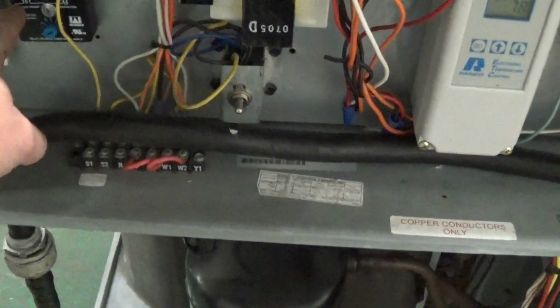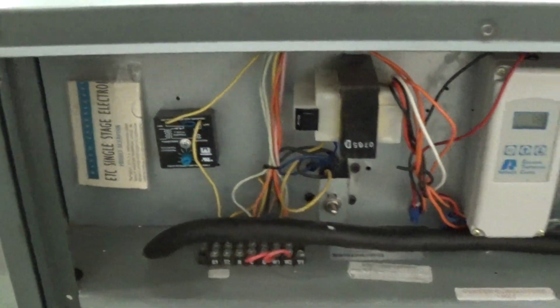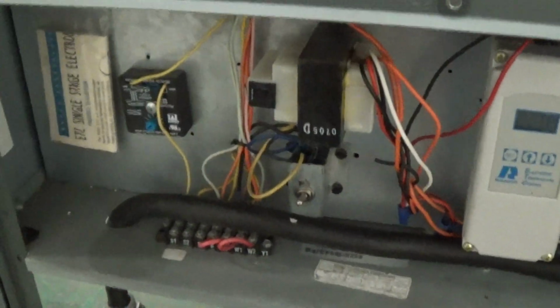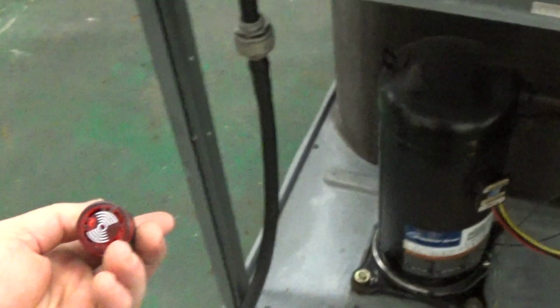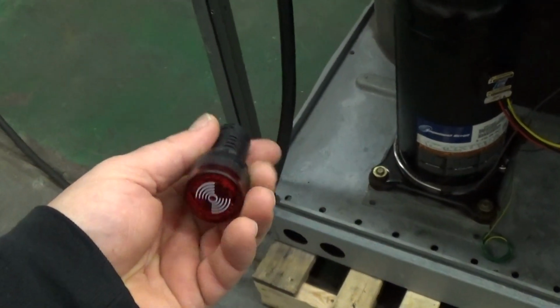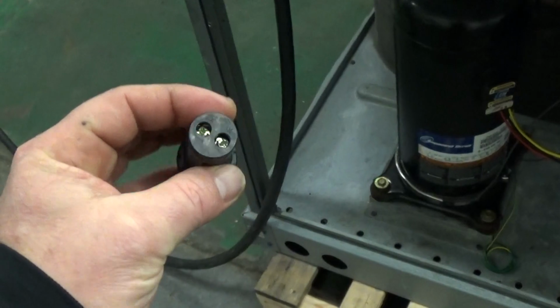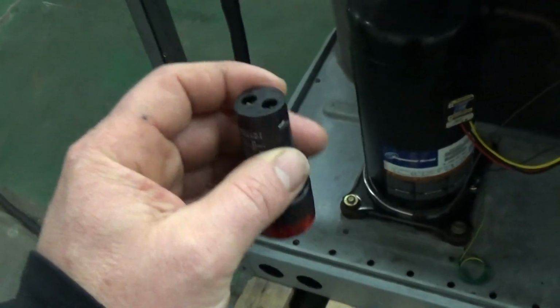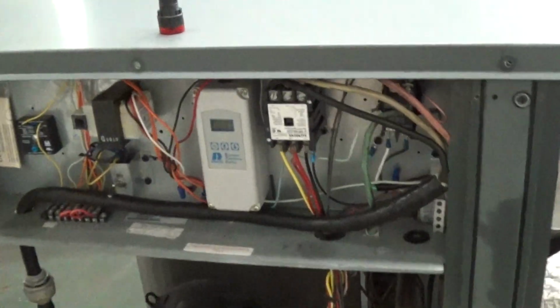And here this is actually a timer that's going to be dedicated to the glycol level switch. We're going to either mount or ship loose with some wiring this alarm and buzzer, and that's tied into this delay timer right here, okay? And so if by chance your glycol gets too low, there's a little float switch in here. It'll set off that alarm and buzzer.